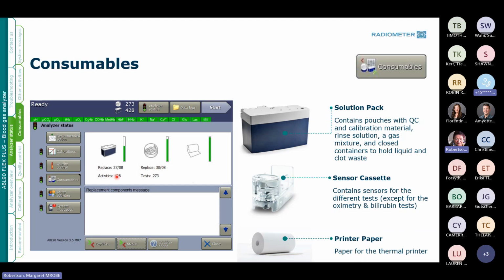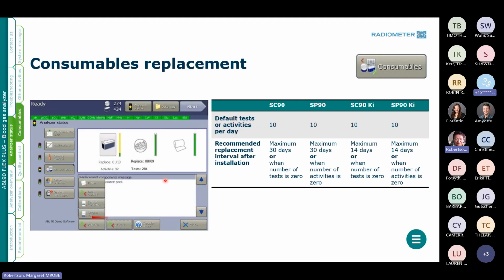Again, on the main screen, analyzer status will indicate when a consumable needs to be replaced and how many activities are left before that happens. So you'd push the consumable button. It'll bring up a screen to show you where you're at. You can see right now on this one, the solution pack needs to be replaced. So we're going to go down to the replace button, select solution pack, and replace the solution pack. These packs and sensor cassettes are good for 30 days on board the analyzer, or the number of tests that come up. So if you have more tests left at the end and the 30 days is up, they expire on the 30 days. So just to give you an idea of that.